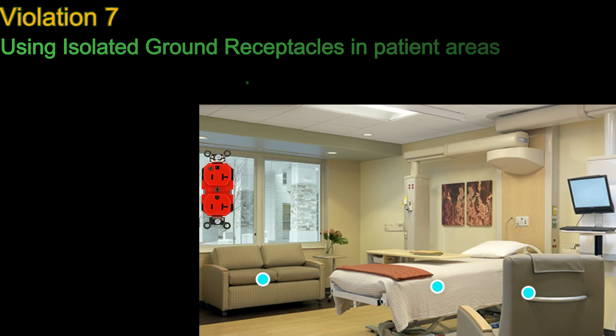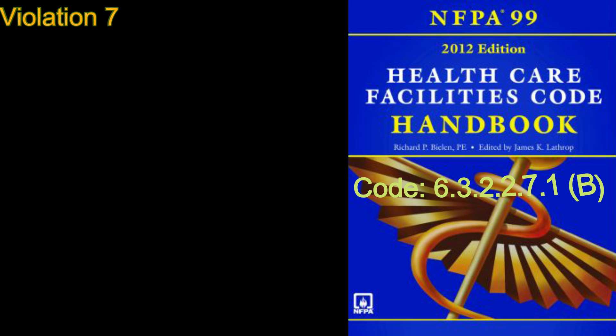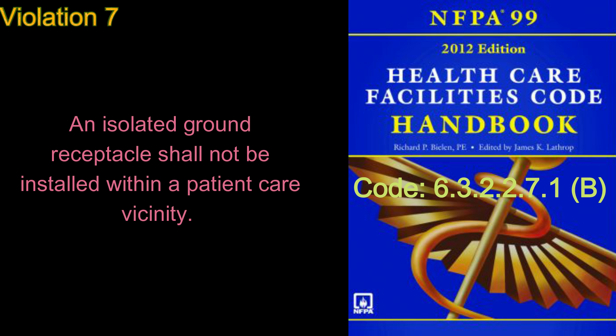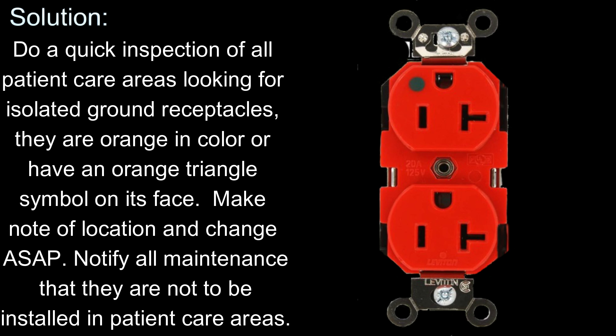Number 7: Using isolated ground receptacles in patient areas. Isolated ground receptacles have been found in patient care areas. Some say the system is on isolated power so they used isolated ground receptacles. However, the primary protection for a patient is the ground going back to the reference ground bus whether on grounded power or isolated power. On isolated power, the line isolation monitor is monitoring any path going to ground. If equipment is plugged into a receptacle that is not referenced to earth ground, the LIM will not be able to monitor any fault that may potentially be going to ground. Code 6.3.2.2.7.1 B — an isolated ground receptacle shall not be installed within a patient care vicinity. Solution: Do a quick inspection of all patient care areas looking for isolated ground receptacles. They are orange in color or have an orange triangle symbol on their face.